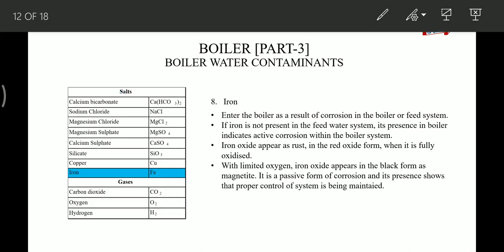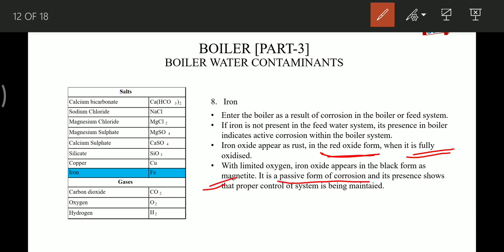Iron enters the boiler as a result of corrosion in the boiler or feed system. If iron is present in the boiler but not in the feed system, it indicates active corrosion within the boiler system. Iron oxide appears as rust in red oxide form when it is fully oxidized. With limited oxygen, iron oxide appears in the black form as magnetite, which is a passive form of corrosion. Its presence shows that proper control of the system is maintained. If the black form, magnetite, is found in the boiler, it indicates that proper water treatment is being maintained.